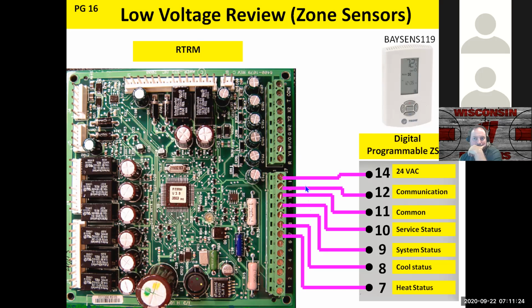And again, when this is wired in, this terminal strip is deactivated. You can't jump out R to Y or R to G and make the system run. You need to remove these wires to do that.